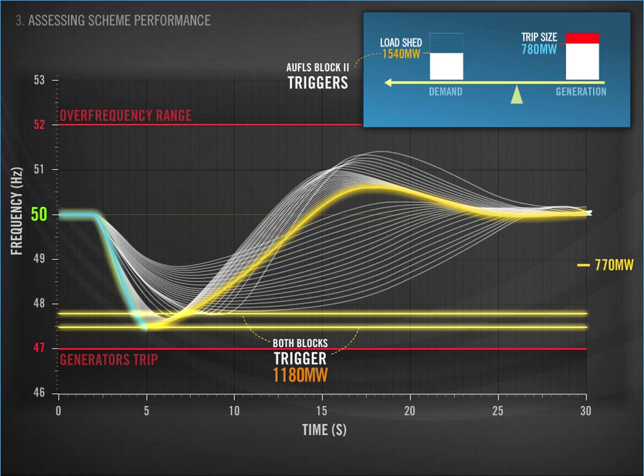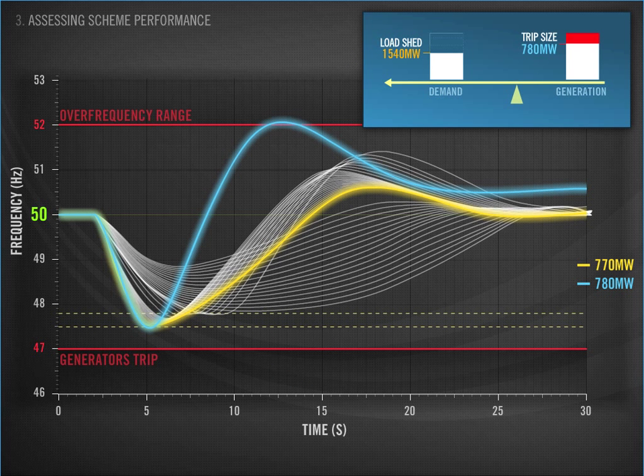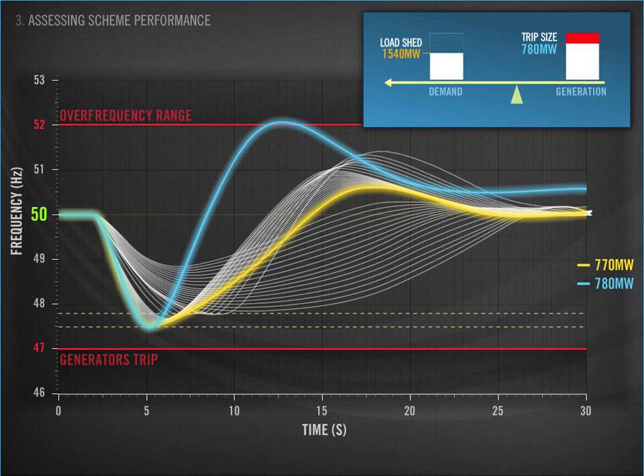Just as if someone jumped off the seesaw really quickly, you now have overshoot. We've reached that top limit of 52 Hz and have gone into the over-frequency range. In terms of scheme performance, that's what we call non-performance. The scheme was unable to prevent the frequency from rising above 52 Hz, which could result in loss of additional generation and system blackout. This is clearly a situation we want to avoid.